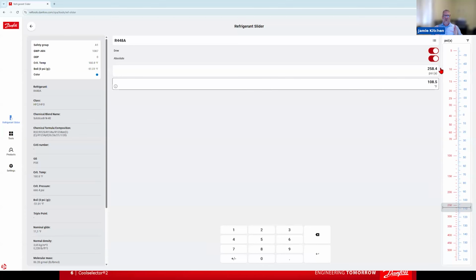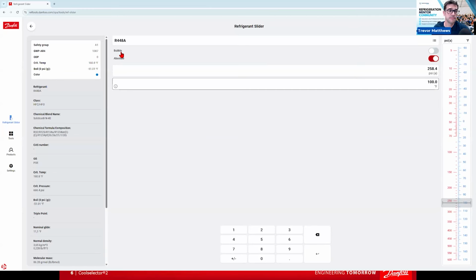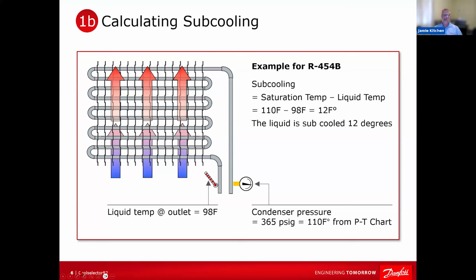So the point here is that as long as you know what you have, remember, information, knowledge is power, right? Follow the steps, follow what the recommendation is. Again, I even had to write it down. Dew point is superheat. Use your dew point value for superheat. Use your bubble point for subcooling. As long as you have access to that information, you are golden, right? You can have confidence in what you're saying.